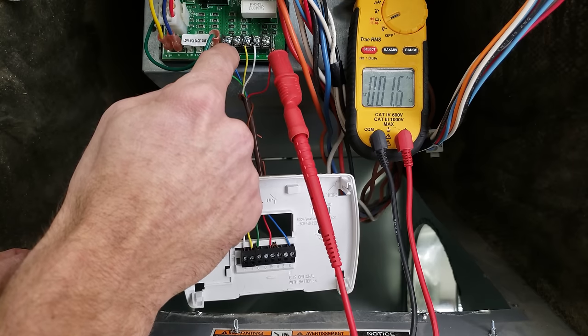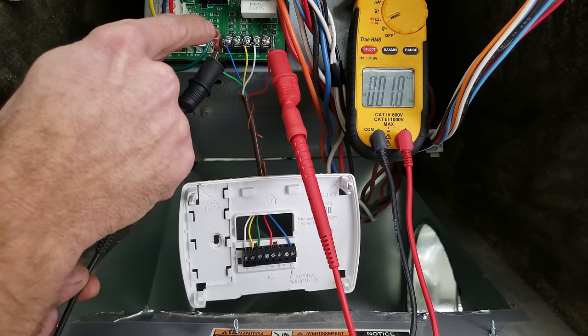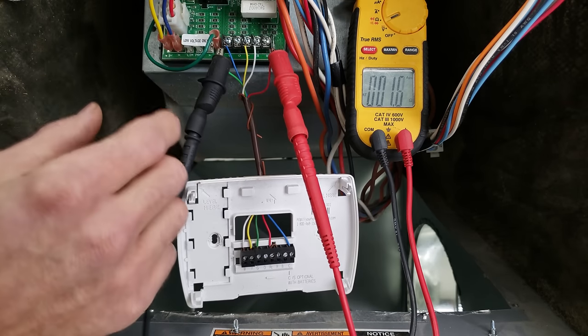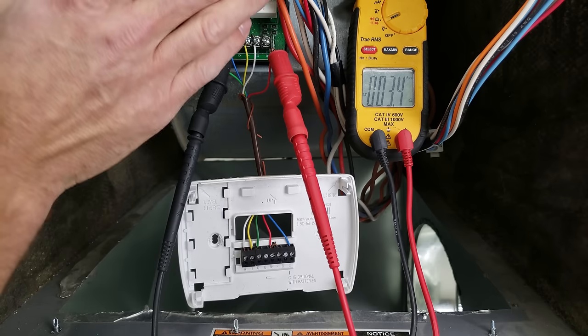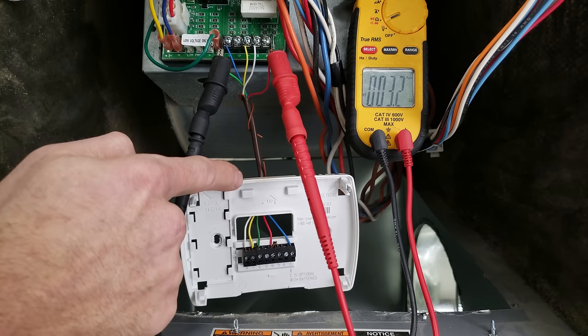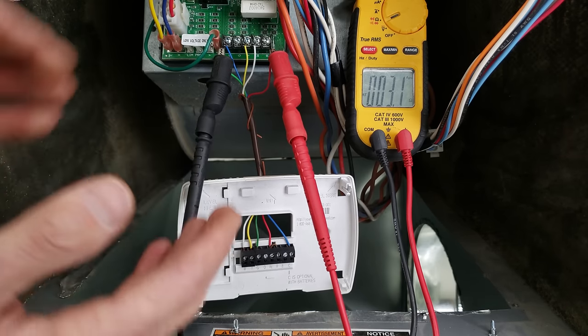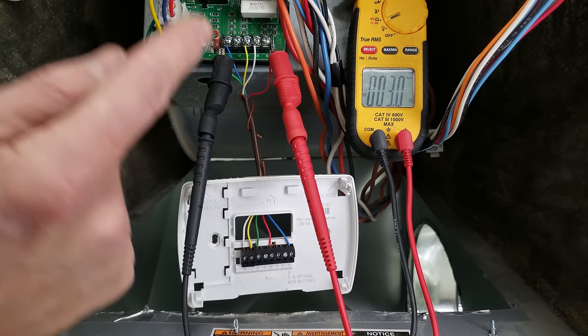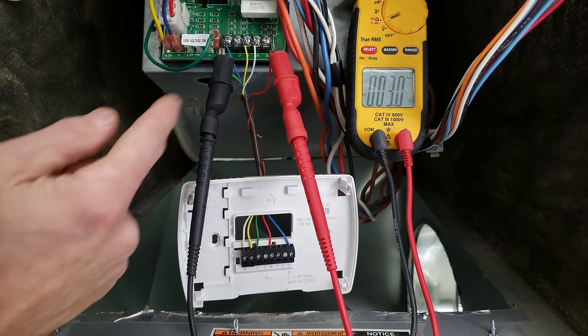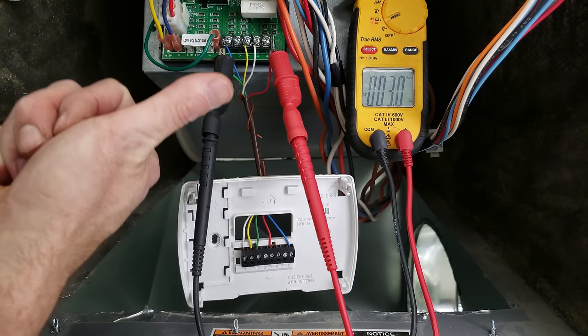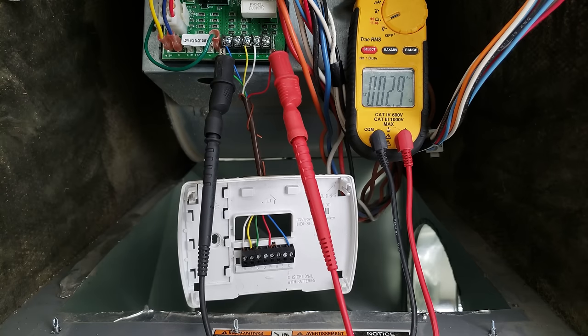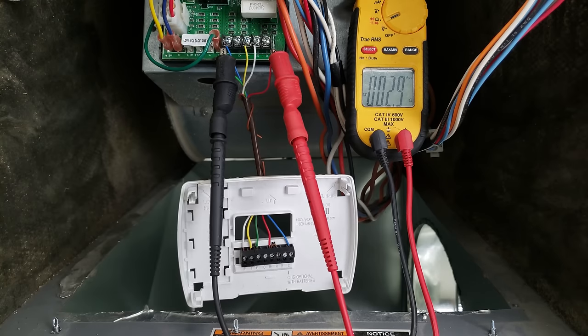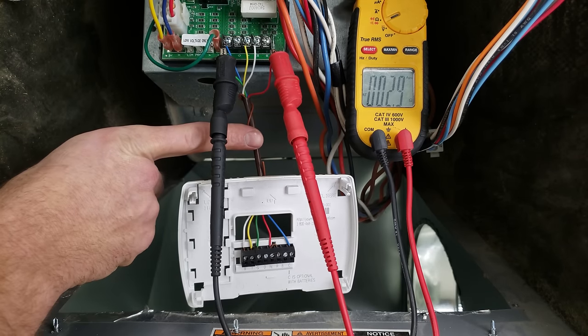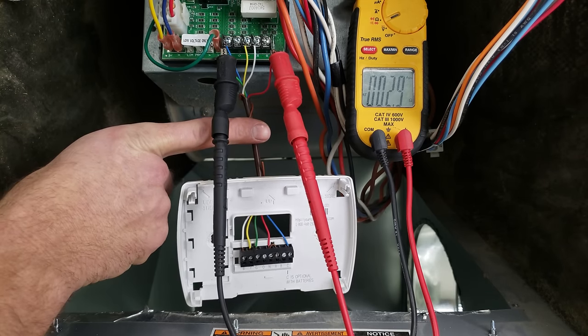And that's the problem with why our control board was getting a 24 volt signal on the G telling the control board to turn the blower motor on. So just remember that the thermostat and the thermostat wiring is really acting like a switch to connect the R wire to one of the signal wires. G, anytime R connects to G, that's for fan. Anytime R connects to W, that's for heat. And anytime R connects to Y, that's for air conditioning mode. So in this case, what we're going to need to do is replace this thermostat wire.